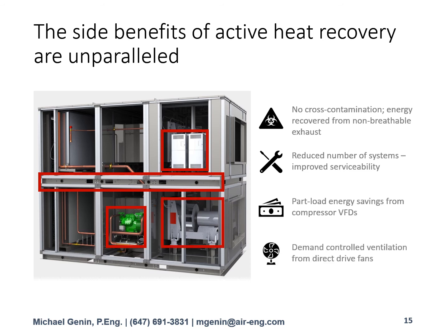making sure you're getting a nice constant supply air temperature. Direct drive plenum fans have become commonplace, but we haven't talked much about the controls on this unit. You can add a CO2 or total air quality sensor, and the controller in this unit will automatically do a demand control ventilation sequence where it ramps the fans up and down. With that, you can realize even further energy savings above and beyond what we've talked about today.